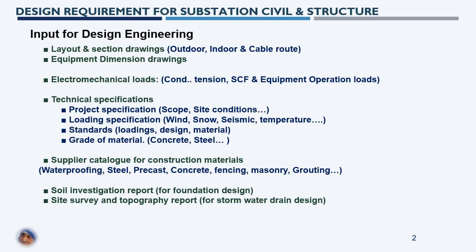Next are electromechanical loads, which comprise conductor tension. Whenever a conductor is fixed between two equipment items or any gantry line, it is subject to tension and load as it is a flexible member. The conductor will have tension pull due to its own weight, and ice or wind impact will also increase conductor tensions. These loads are generally calculated by an electrical engineer, as they involve electrical requirements needed to arrive at conductor tension and short circuit forces (SCF).